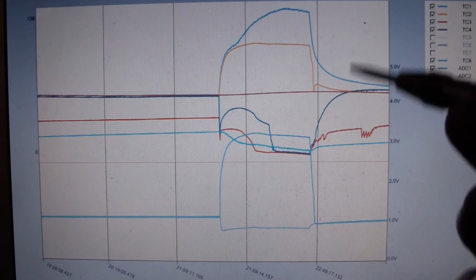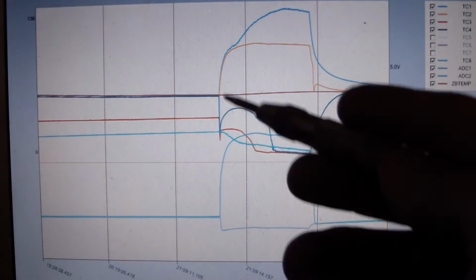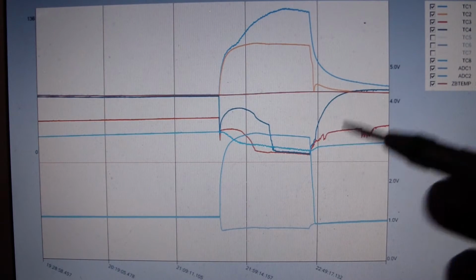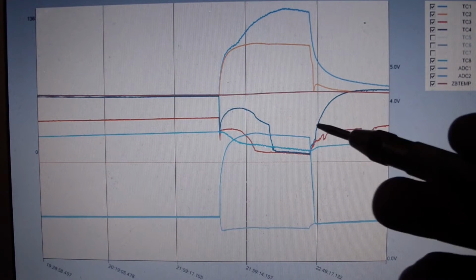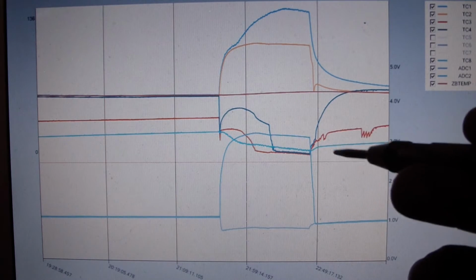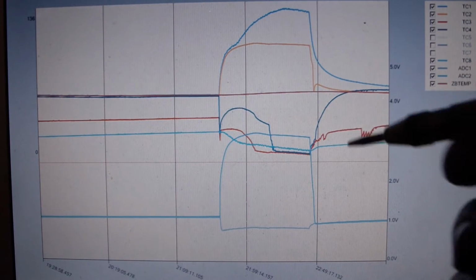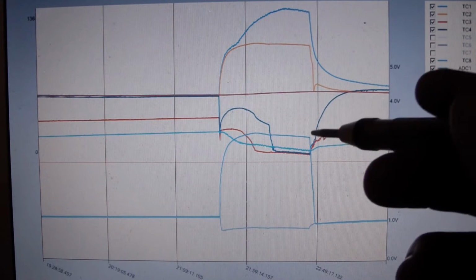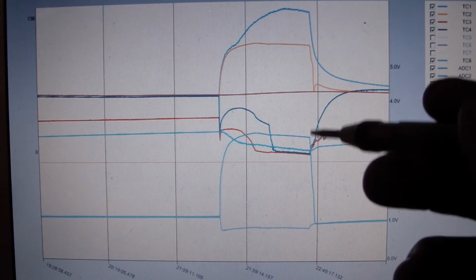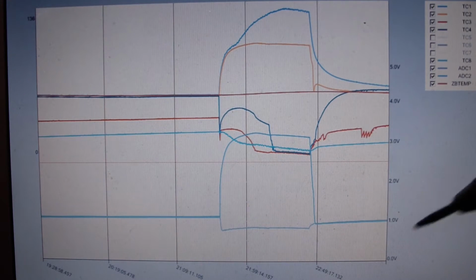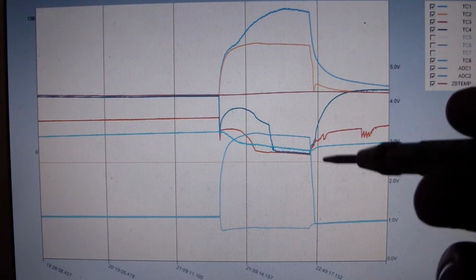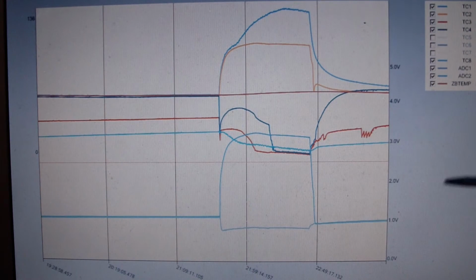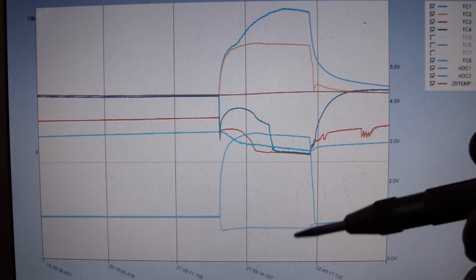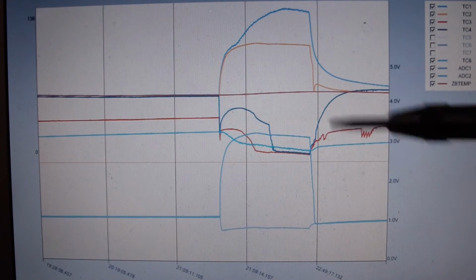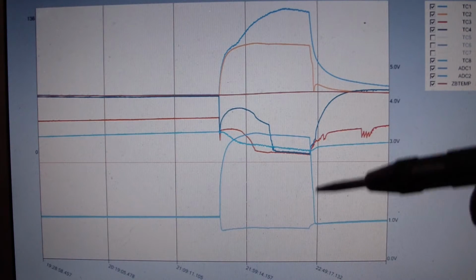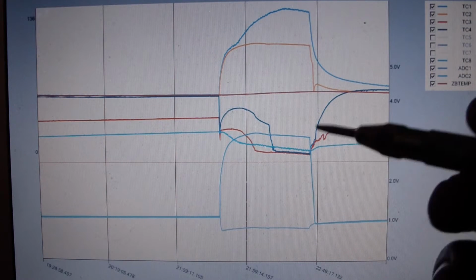Just to begin with, I'd like to point out that to understand the start of this, you have to understand kind of the end of the last cycle. During the last cycle, at the end of this one, since this one looks like any other one, we had some liquid refrigerant that's built up into the high side, and whenever the compressor shuts off, that liquid plug is pushed into the low side. So we have probably a good bit of migration of the liquid refrigerant into the low side. Also, the low side's cold as well, so even during that off time, a lot of vapor is going to end up condensing into that low side. So probably the majority of the liquid refrigerant is in the low side at the startup.